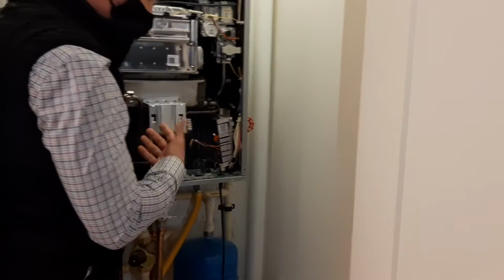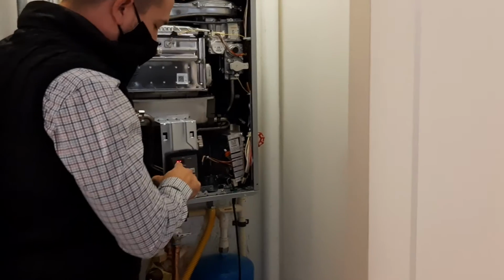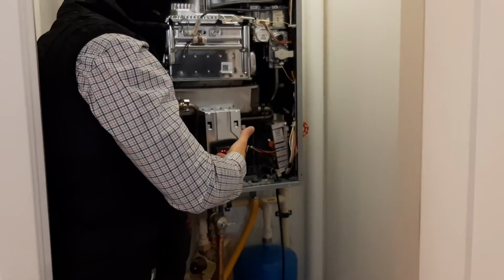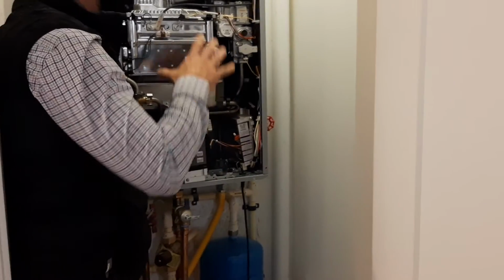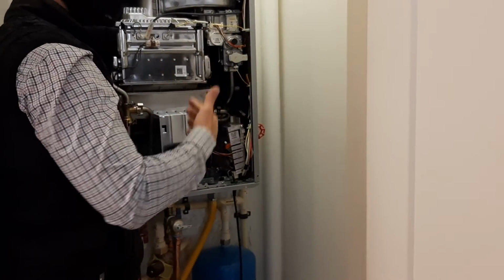So if you come back in 6 months on another complaint, you check the error history. If there's a new error code, you'll see it. If it still says FF, it's not an error — it might be, like you said, a leaking check valve or something else.